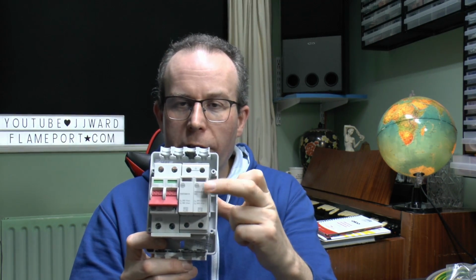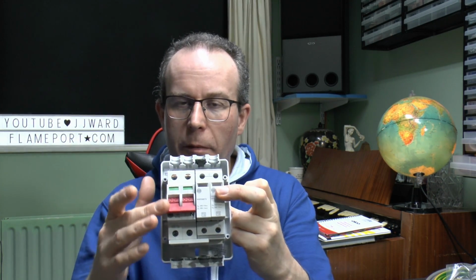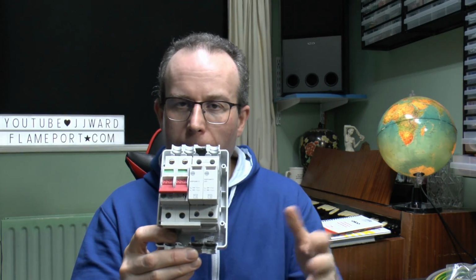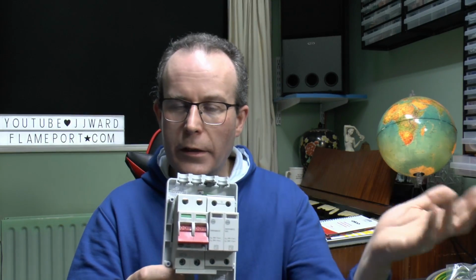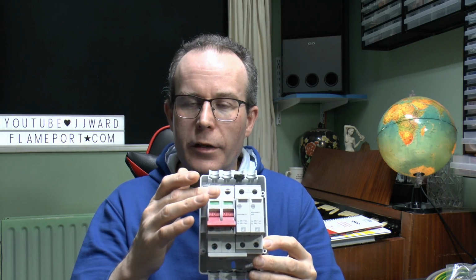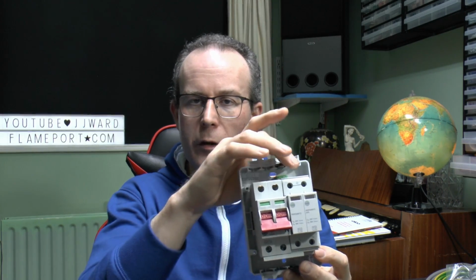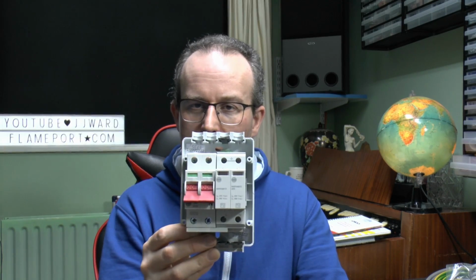So that's surge protection devices. And the length between the surge protection device and the conductors that supply the installation is what's really important here, not the length between the thing itself and the meter, fuse or anything else. So in this particular case, this is a standalone unit. The supply comes in the top, comes out the bottom, goes to your consumer unit or panel or whatever. Surge protection device is right there next to those conductors, so the only distance involved here is just those 2 tiny short bits on the back here. And the earth on this one comes in the top and then goes out as well, so that's pretty much 0.